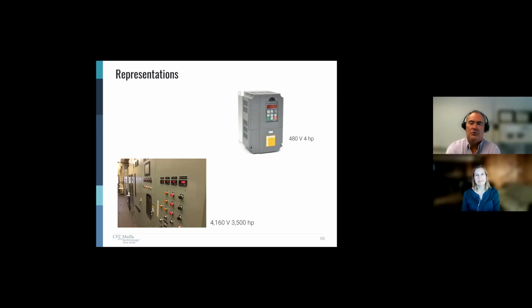So here's a couple of pictures. The first one is a little 480 volt, 4 horsepower VFD. Very common. You see them hanging on the walls everywhere. This one does not have a disconnect or a bypass. That can be added separately. Versus the one on the lower left, and this is for that 4160 volt, 3500 horsepower motor that we looked at earlier. This thing is the size of a house, literally. It's kind of hard to tell in this picture, but there are about 4 sections of cabinets there, and the 2 on the right are the control sections, and the 2 on the left are the driver sections.